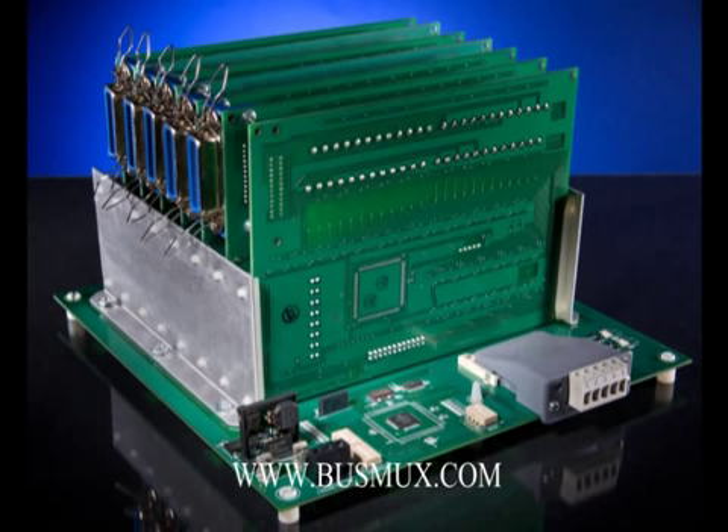The BusMux uses what we like to call open technology, meaning it will accept standard thermocouples, 4 to 20 milliamp or millivolt signals. It then multiplexes an unlimited amount of signals onto any standard bus network, such as DeviceNet, Ethernet IP, Modbus TCP, Profibus, and many more.